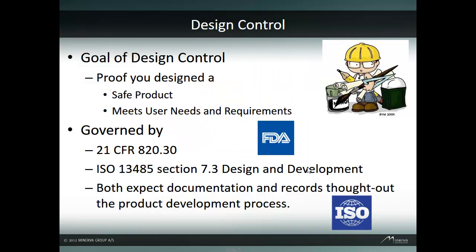The goal of design control regulations is to prove that you have designed a safe product and that it meets user needs and fulfills all the requirements. The specific FDA regulation that talks about design control is 21 CFR 820.30 and ISO 13485 Section 7.3 Design and Development. Both expect documentation and records of design throughout the product development process.